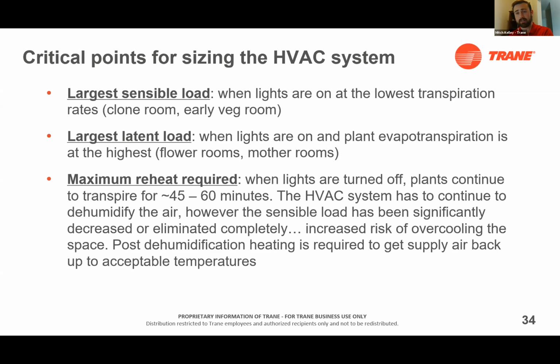One of them is by using a desiccant to move the moisture to a different airstream. It's often very expensive and a very high temperature process. The other way is to cool the air down to below its saturation point to remove the humidity from that block of air. That's what's traditionally done in any kind of series dehumidifier that you see.